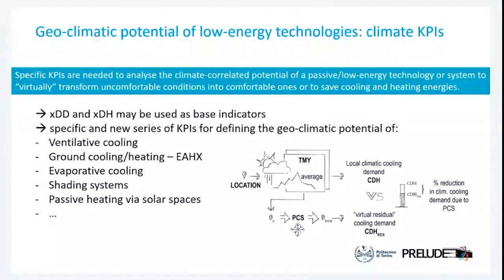For example, for evaporative cooling, the applicability is based on the local wet bulb temperature, without pre-treating the air from the humidity point of view. For ground cooling or heating, we are speaking about earth-to-air heat exchangers, so low-enthalpy horizontal tubes with air, for example. It's clear that if we don't activate the soil in a specific way, the air potential is based on the soil temperature around the tube, which is given by the density, by the thermal properties of the soil, and by the depth, and other variables. On the ventilative cooling side, clearly the heat sink that we use is the external air, the outdoor air, if we don't pre-treat it. So that's the variable that we need to take into account.